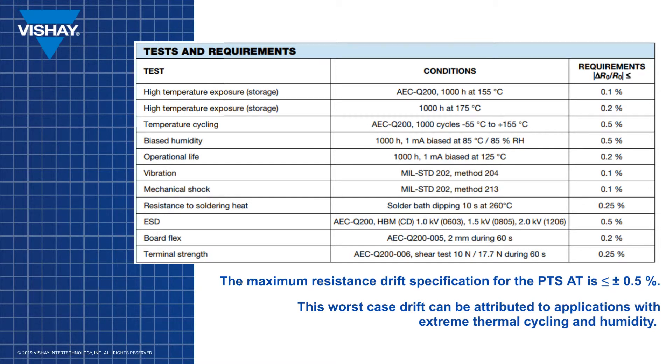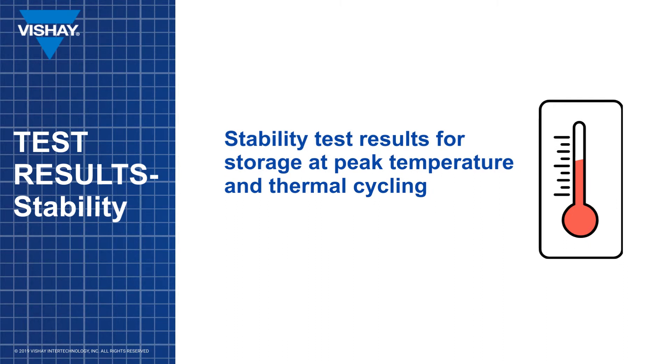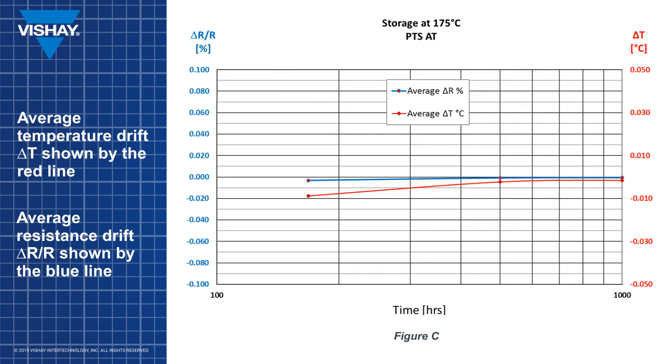However, for most applications, the typical performance is much better than the maximum specified stability. As previously stated, the PTS-AT is excellent in maintaining its temperature characteristics over time when subjected to extreme conditions. On average, the temperature drift specification for the PTS-AT after 1,000 hours storage at peak operating temperature of 175 degrees C is negligible at 0.01 degrees C as shown in figure C.